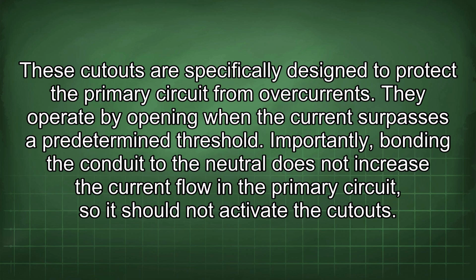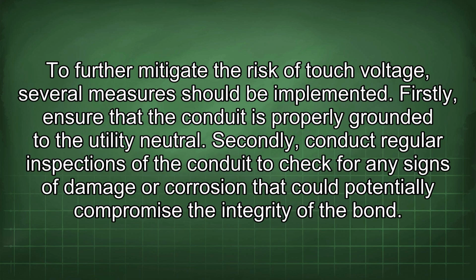They operate by opening when the current surpasses a predetermined threshold. Importantly, bonding the conduit to the neutral does not increase the current flow in the primary circuit, so it should not activate the cutouts. To further mitigate the risk of touch voltage, several measures should be implemented.